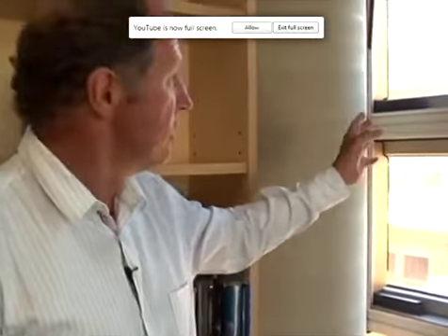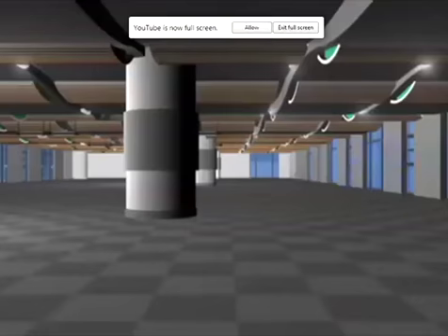It's called a night purge. If we open those windows for 4 hours at night during the summer, we use the cool air that flows in to cool down the concrete ceilings above me. This provides us with a saving of about 20% of the energy in the building.